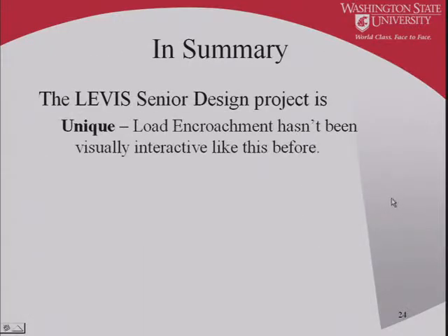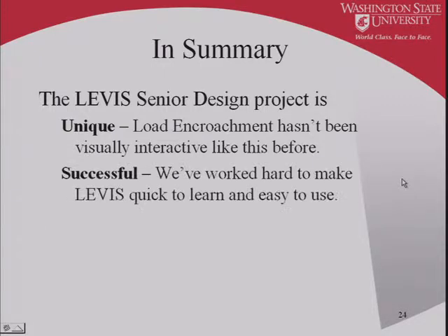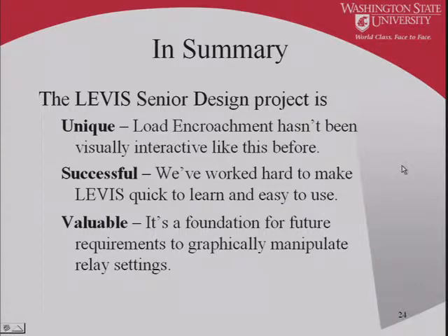So in summary, I've got to say that this is unique. Load encroachment hasn't been done visually interactive like this before. It's cool. It's successful because we've worked hard to make it quick to learn and easy to use. It's not just thrown together. We've gone through it a couple times. And it's valuable because I get to work on it this summer, and SEL relays will benefit from this. Customers will be able to set load encroachment more effectively.